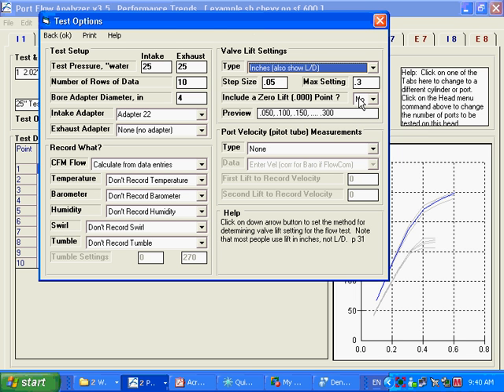Do you want to include a 0 point? Typically you want to do that if you're going to record leakage. Leakage is what does the head flow when the valve is closed. And any flow you get when the valve is closed must be coming from leaks, sources of leaks. And it's just a way of correcting the data. Ideally, you want leakage to be very close to zero. If it's not, you should probably try and find the source of the leaks and fix it. But measuring it and correcting for it is something you can also do.